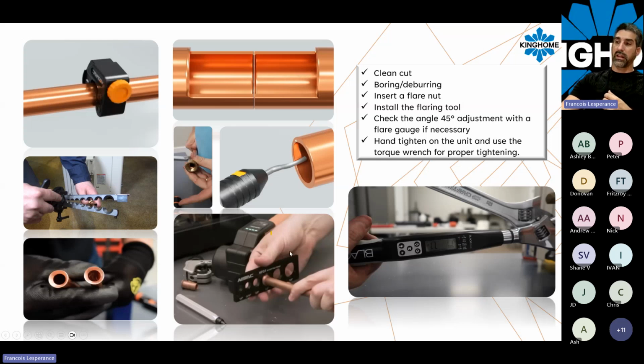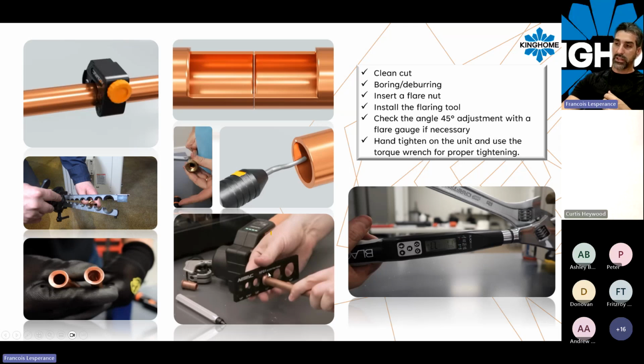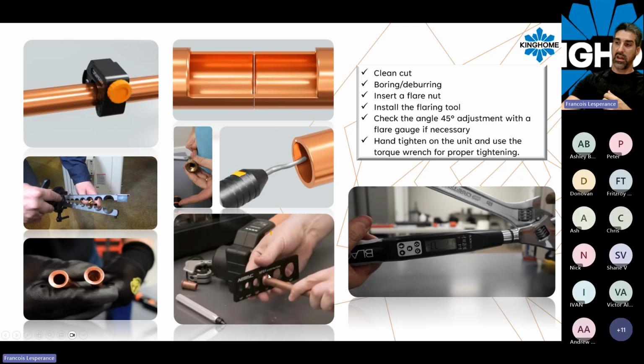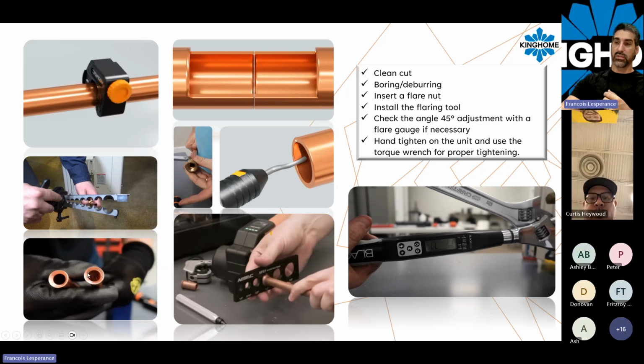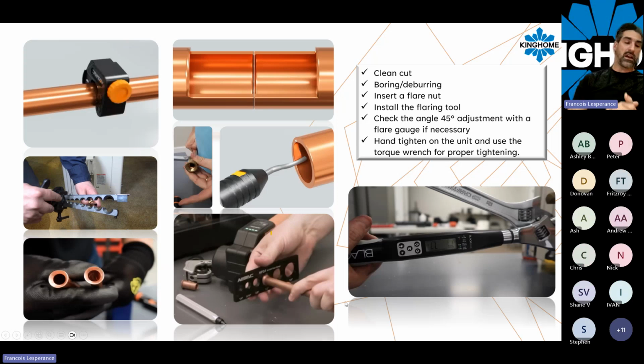You can also use a flaring gauge to make sure the circumference of that pipe is big enough, or sometimes too big. Because if it's too big, the portion where the copper is sitting on that valve is reduced. So sometimes when the pipe is moving, because you can have some vibration coming from the compressor, you can have temperature change, because the copper will react to hot and cold temperature. This is normal stuff happening, where the copper can expand or contract due to temperature change.